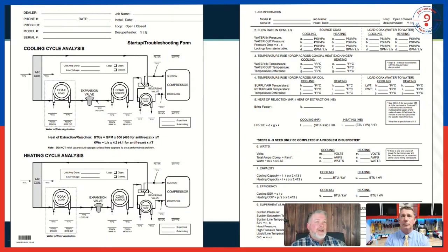And again, I relate that back to this: if you don't know you have flow across your condenser with a geothermal heat pump, that's the same as if you were to go out to work on an air conditioner and you didn't know if the condenser fan was running. Exactly. So we want to make sure we know what our flow is. The next portion of that is the temperature rise and drop across the heat exchanger. So we want to know what our water temperature in and out is on that. And then, of course, our air side as well. We want to know what that air side delta T is doing. Once you get all those numbers, number 5 on there, which again, it's kind of hard to see, but it's right in the middle of the page on the right-hand side, walks you through the formula to do the heat of extraction, heat of rejection analysis that we just talked about. Yeah. And again, that's simply delta T on the water side times GPM times the fluid factor.